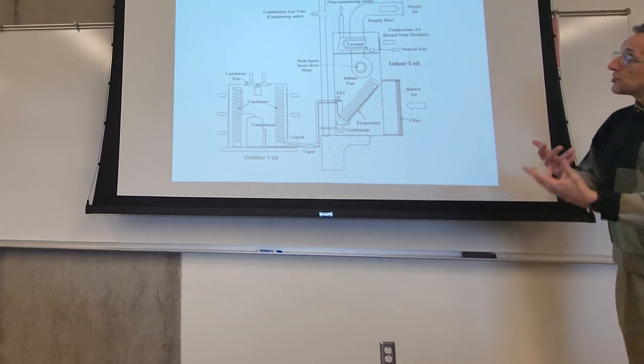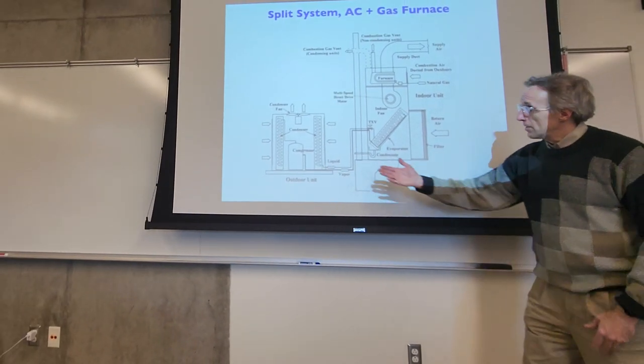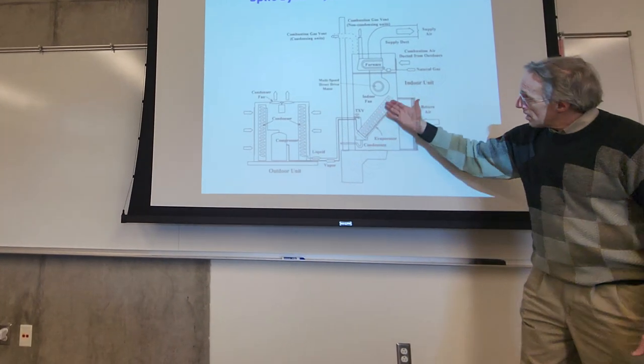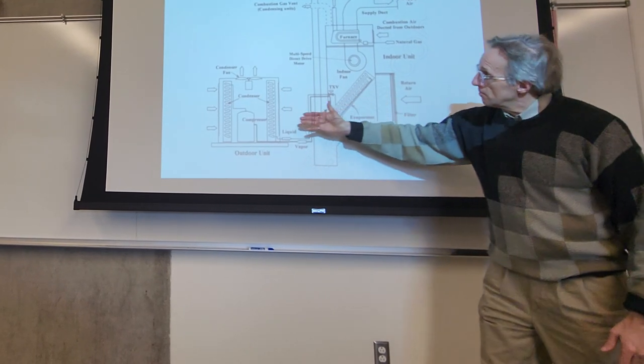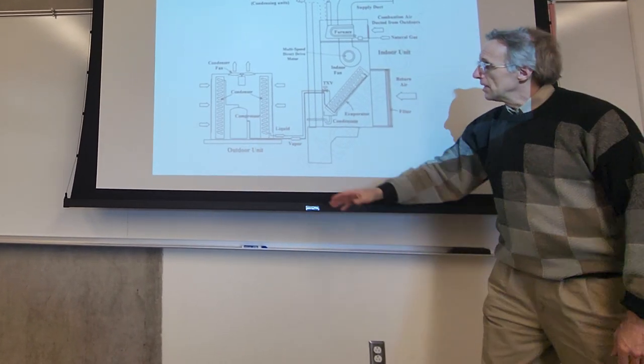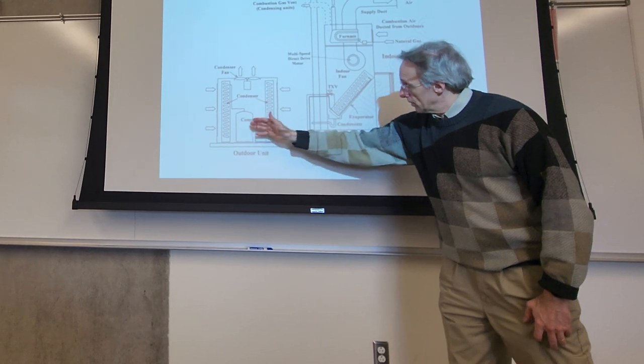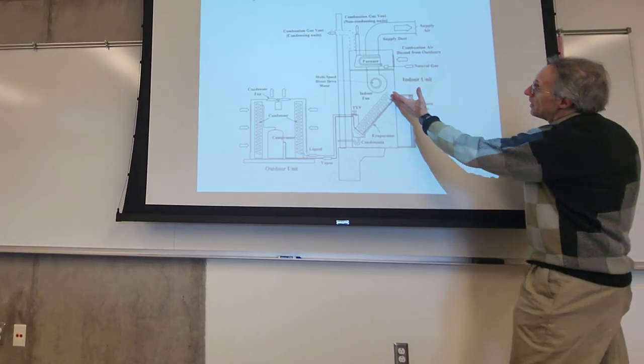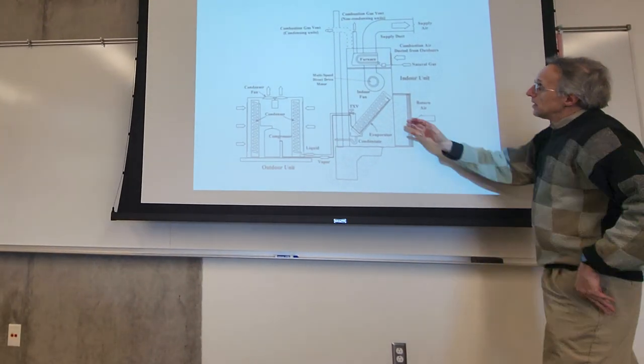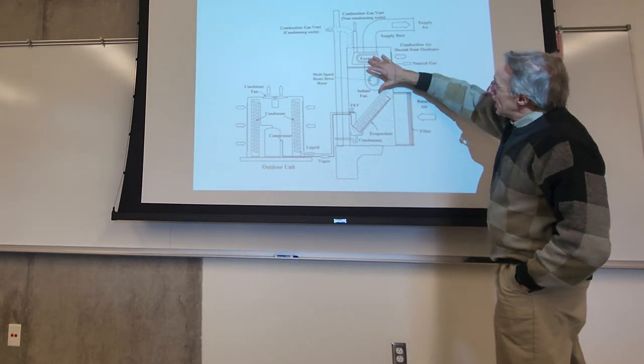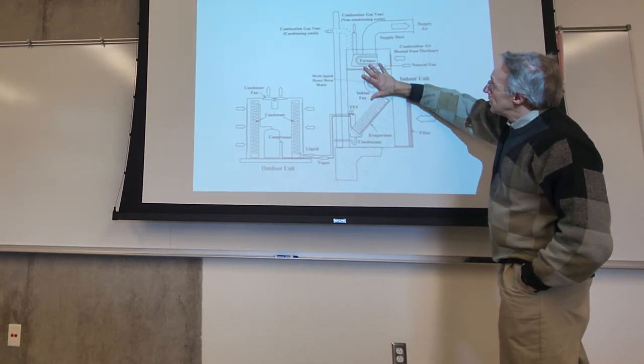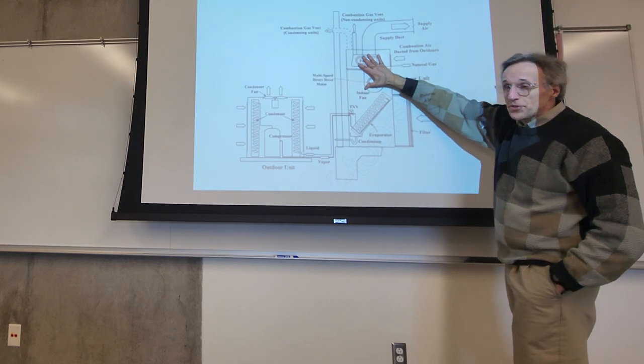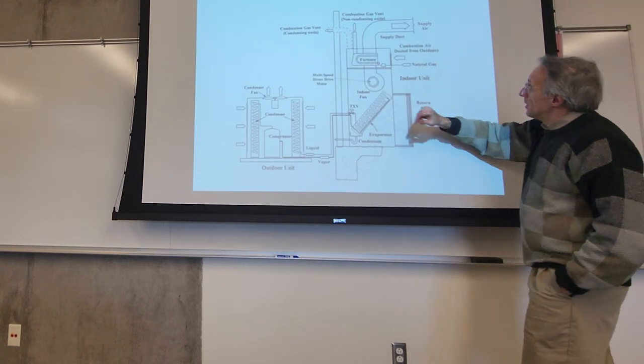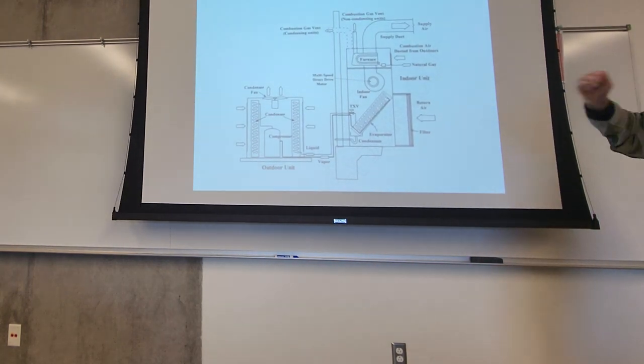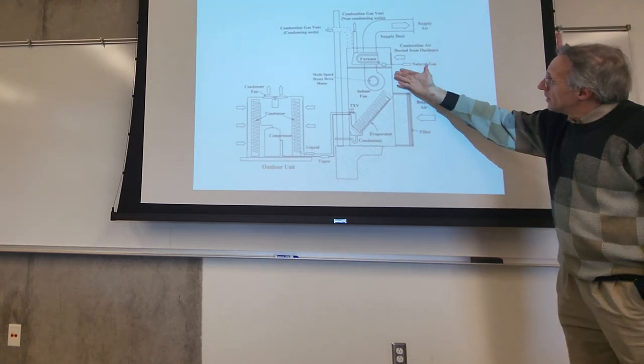In this situation, if it's just an air conditioner, all it does is air cooling. Then we've got a permanent evaporator in here and a permanent condenser out here, and the compressor is also located out there. And then the air handling system supplying our building has a fan and a furnace built in. Showing the natural gas hookup here.